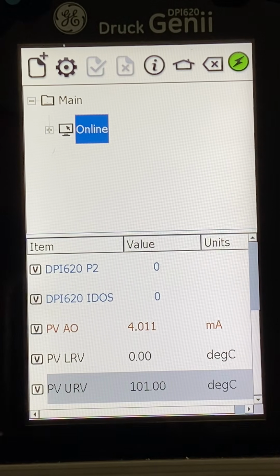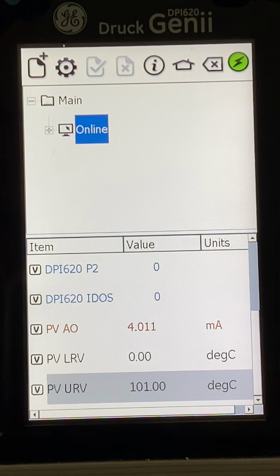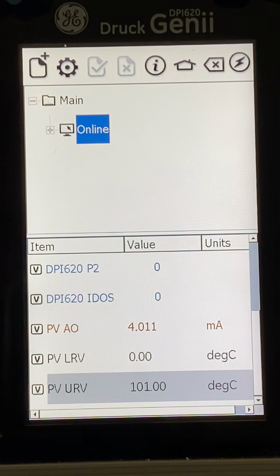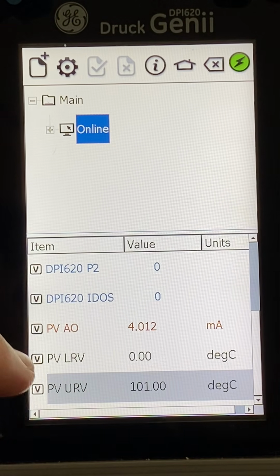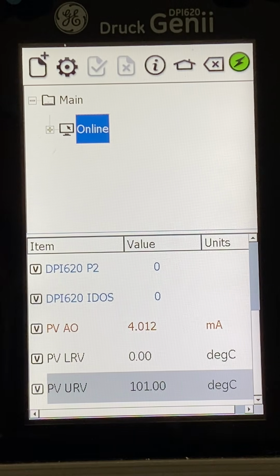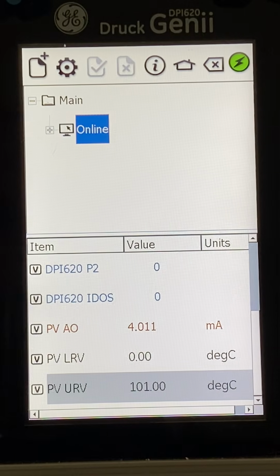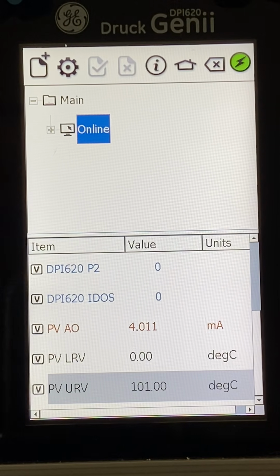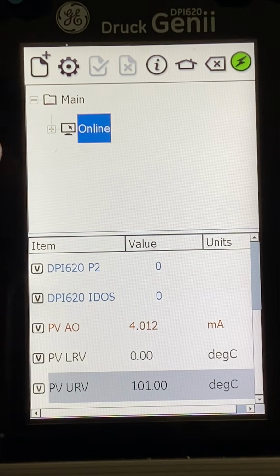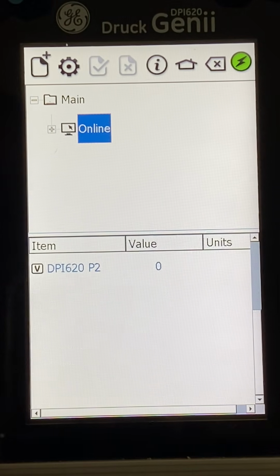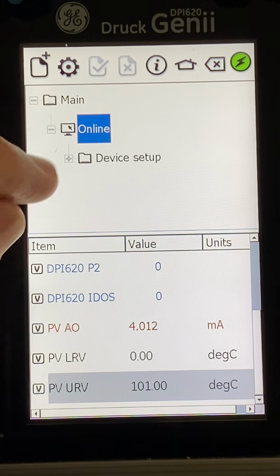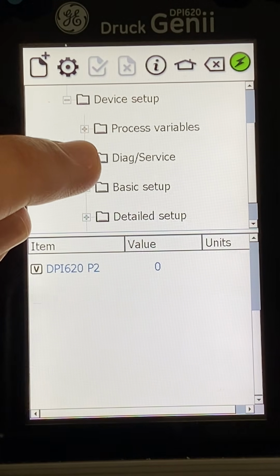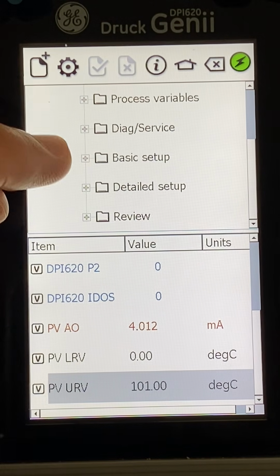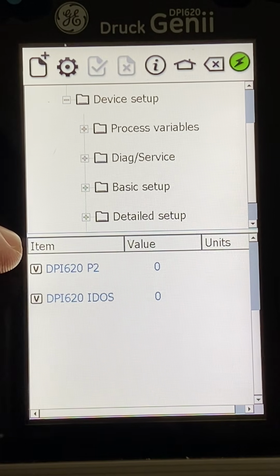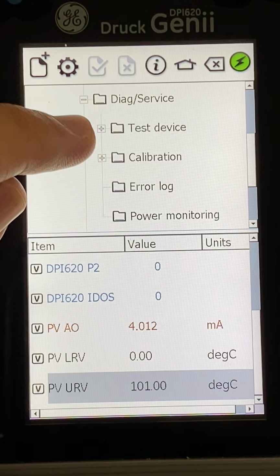The other option is very useful because we have a calibrator here with the communicator. We have standard values for the readings. So instead of inputting the LRV and URV by hand, as a keypad input, I can do this from the calibrator on actual value. So I can apply the values of the URV and LRV. Here from the online device setup, I have process variables, diagnostics, basic setup, detailed setup, review. So I have a lot of functions. Let me go for diagnostics and services.